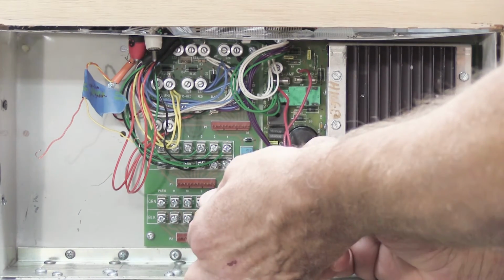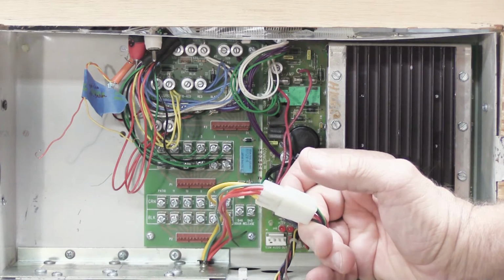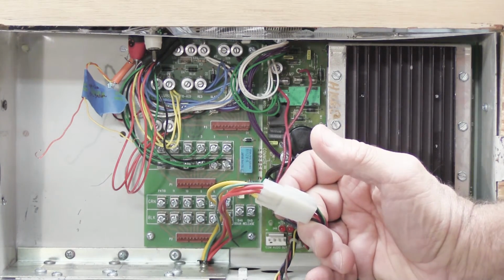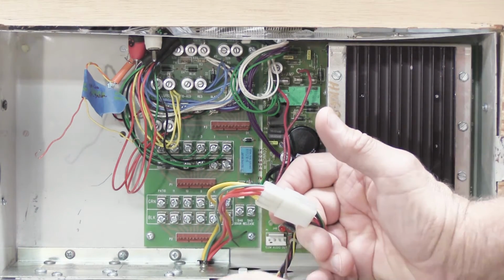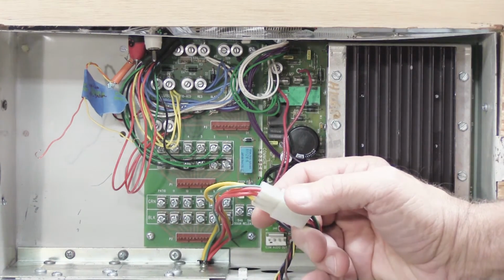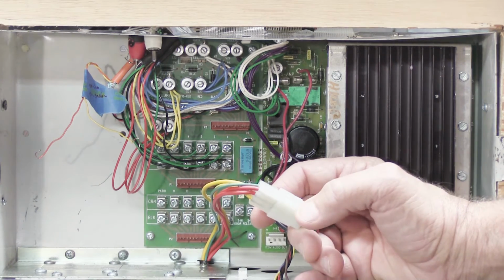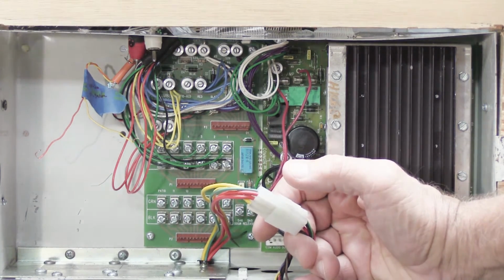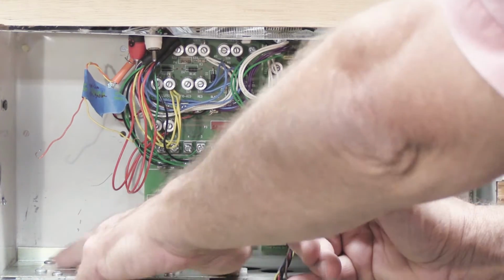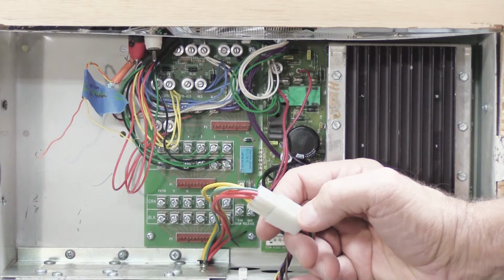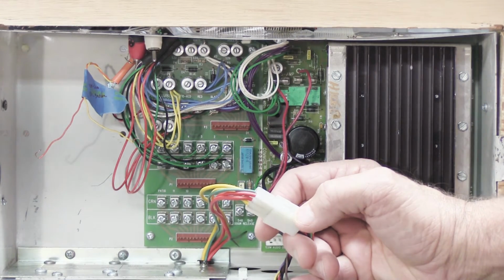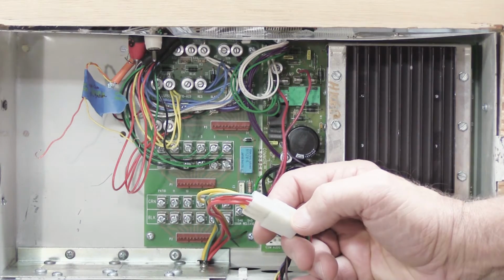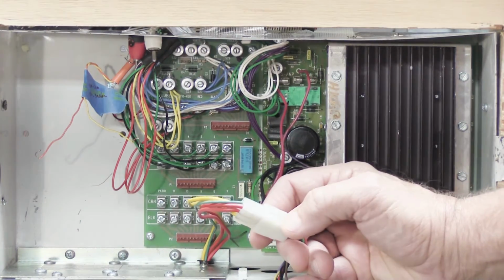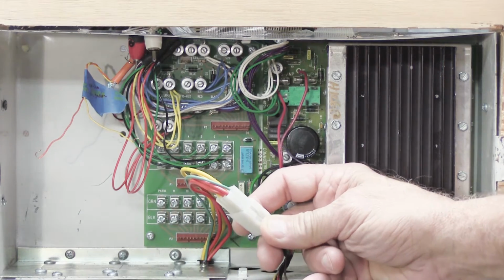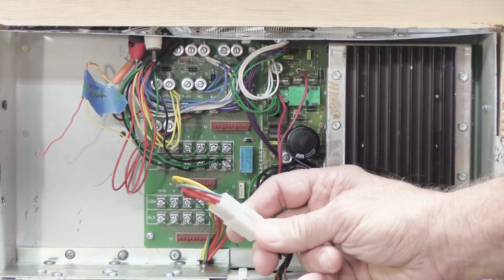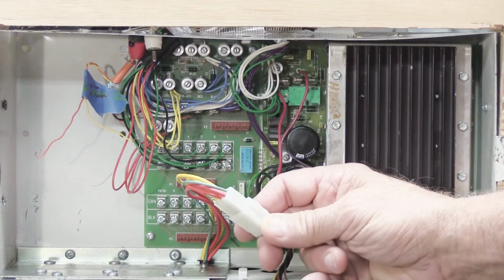If you unplug this, and more importantly, plug it back together while the circuit breaker is turned on and the transformers are powered up, you run the risk of blowing the fuses in the transformers. If you do that, your transformers go dead. Then you have to disassemble all of this, no small thing to do, and then ship the transformers to me so I can open them up, replace the fuses, and send them back to you, and then you have to put this all back together. That's a whole lot of effort and trouble, not to mention the extra expense, because you didn't want to walk over and flip your circuit breaker panel off.